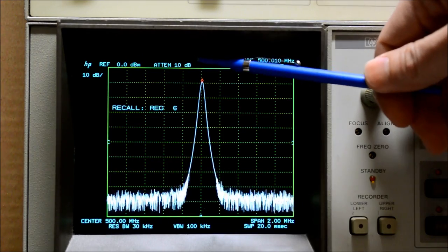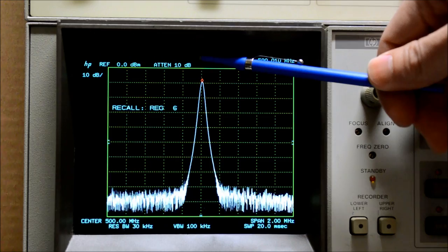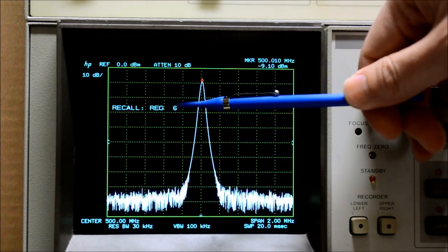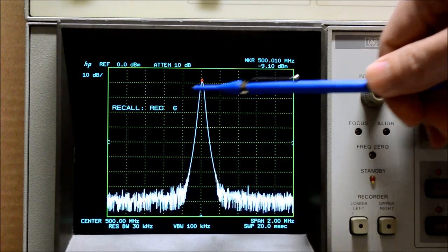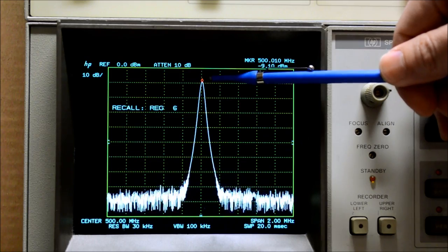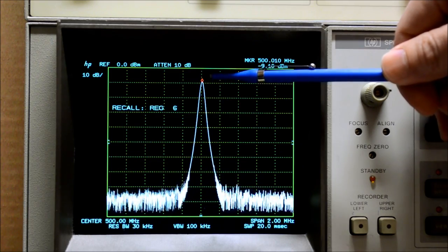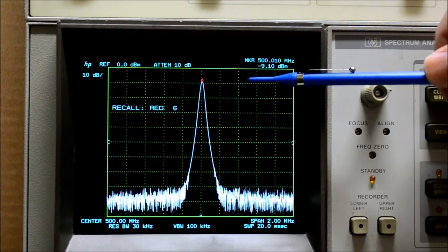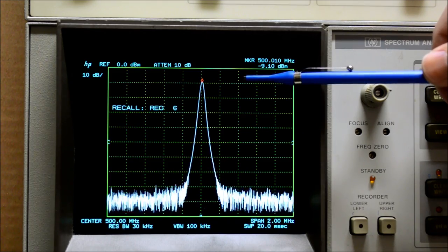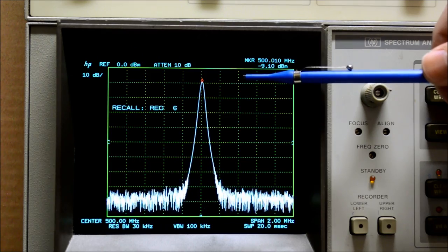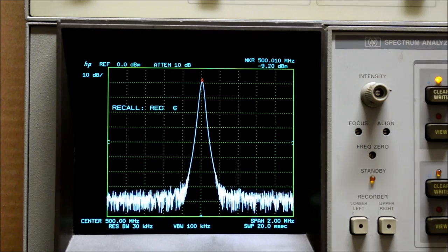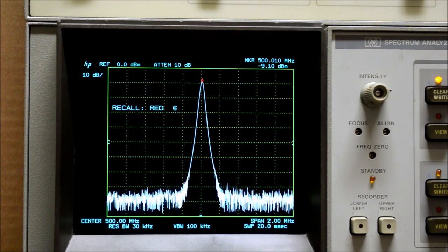The bitmap font with hand-optimized glyphs gives better clarity over the original vector font when rendered on a VGA LCD panel. The marker is enlarged and painted in red so that it is easier to find. The NewScope display scheme has resolution enhancement that takes advantage of the 1024-point original resolution of the 8566A display. It gives a smooth curve with reduced jaggedness. We'll look into other improvements later in this video.